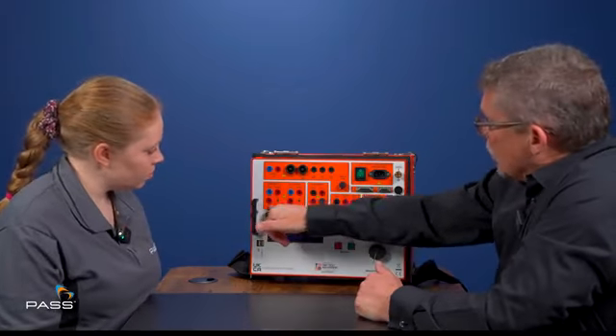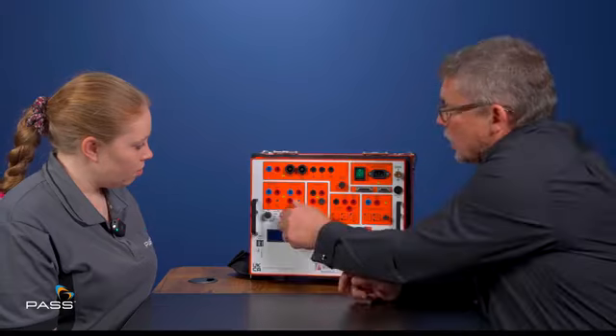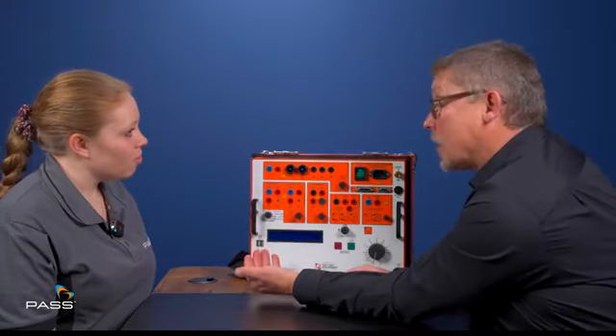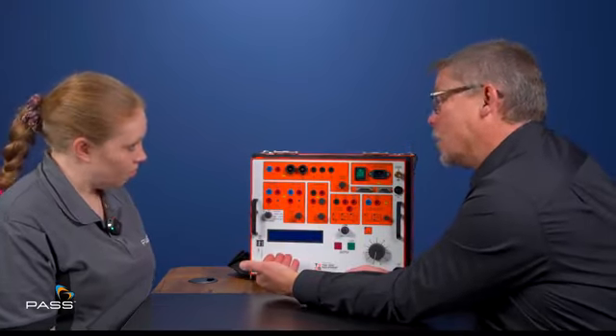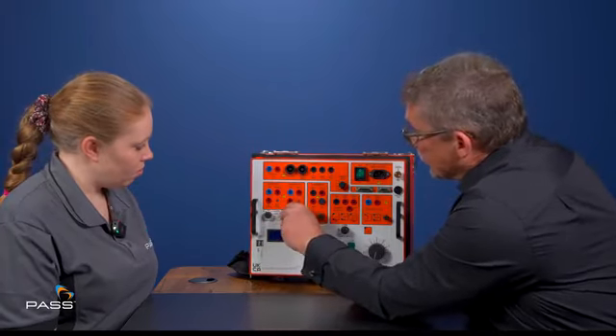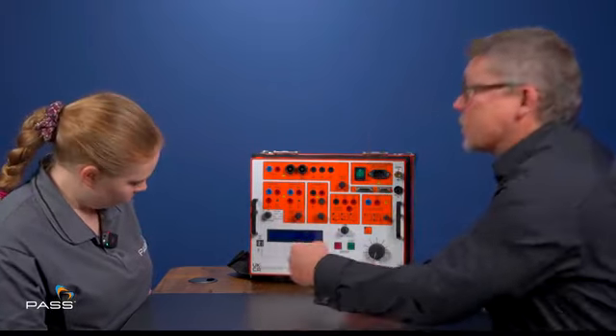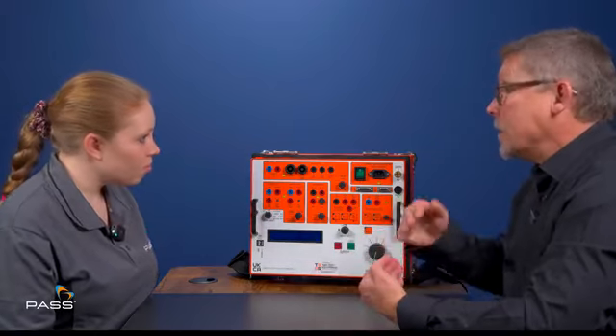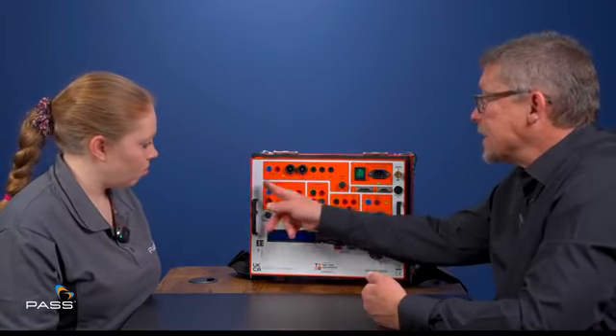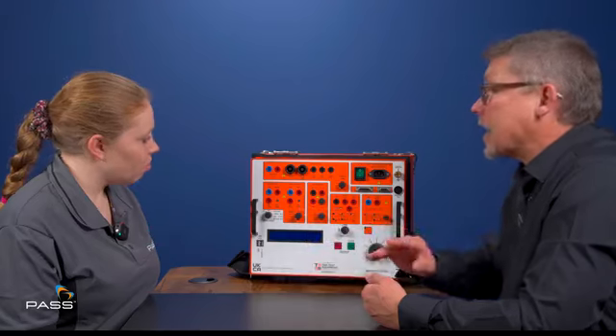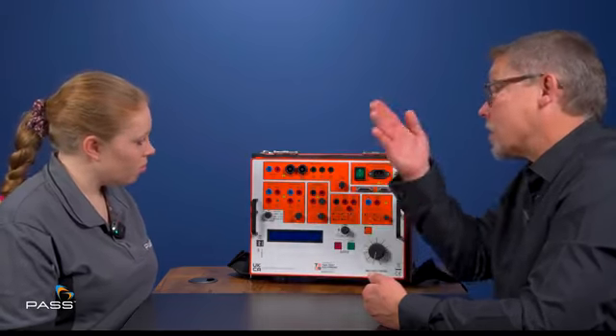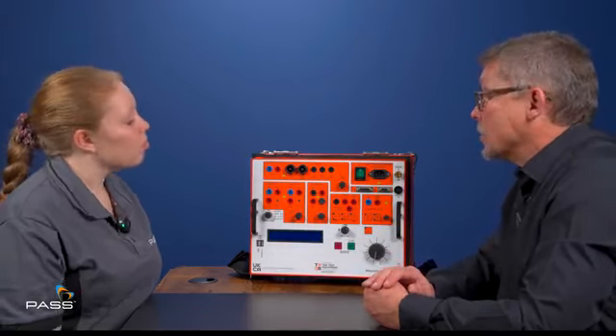So this is our contact timing section. The contact timing section allows us to time, essentially we're timing relays normally. And what we've got is the first point there, we've got internal start. So that means when I hit that button, the timer will start. When it sees a change on either of these contacts, the timer will stop and will also cut the power to the main outputs. We have one contact.